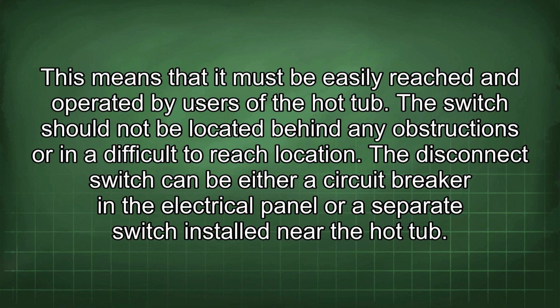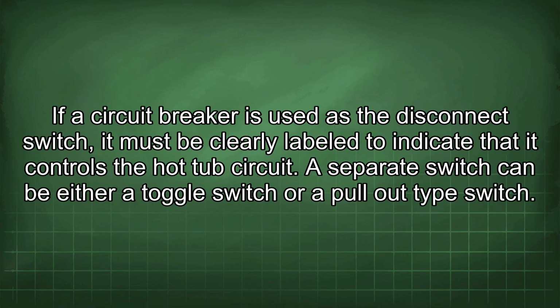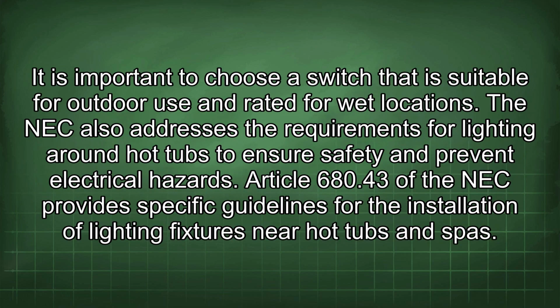The disconnect switch can be either a circuit breaker in the electrical panel or a separate switch installed near the hot tub. If a circuit breaker is used as the disconnect switch, it must be clearly labeled to indicate that it controls the hot tub circuit. A separate switch can be either a toggle switch or a pull-out type switch. It is important to choose a switch that is suitable for outdoor use and rated for wet locations.